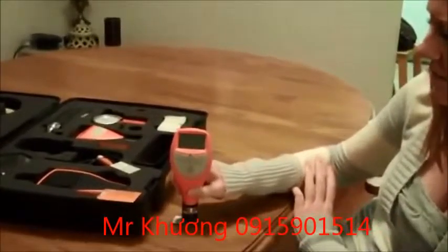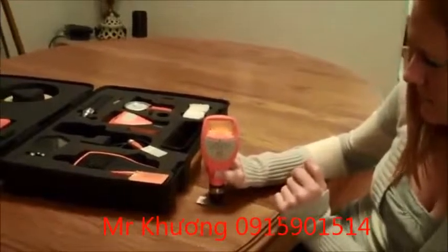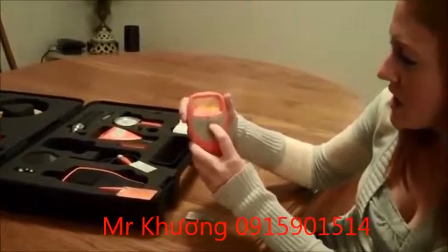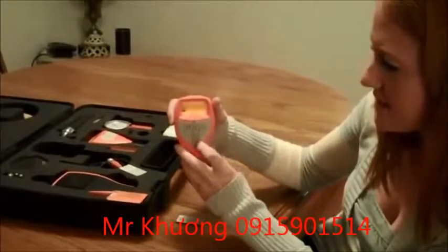All right, so we got readings of 9.8 mils, so we're just going to use the up arrow to have it read 9.9, and then I'm going to press the set button. Then we will be prompted to place the probe on the uncoated base. So I'll take my shim off of the base, and I will test that 3 to 5 times as well. All right, so I'm getting readings right around 0, so I'm going to press the 0 button and then set.